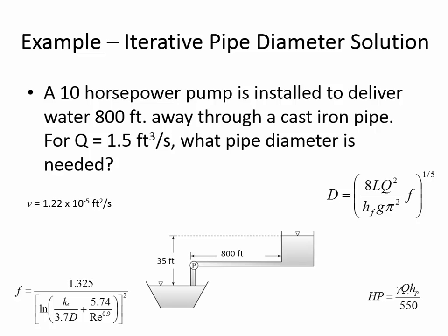The physical interpretation of this pump head is that this pump is essentially lifting the water 58.79 feet. It's having the same effect. It's not actually physically lifting the water, because you can see this pump is just in one location, so it's not like it physically lifts the water and then it flows downhill. But it's kind of like saying, if you had a reservoir, how tall would that reservoir be? How much pressure is the pump adding?